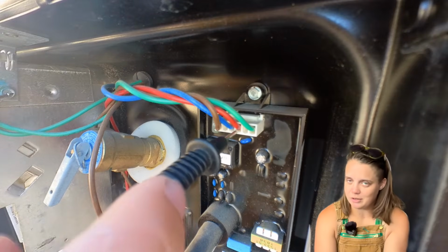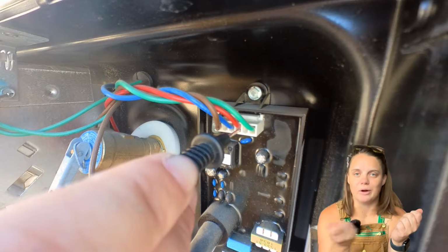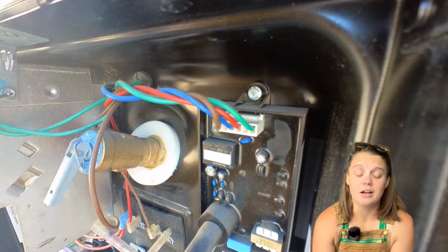So I have yet to have the igniter be the problem on a water heater, but hey, it does happen. So assuming that we've got 12 volts on brown, 12 volts on blue, and we are hearing a ticking noise coming from the igniter, then the next stop on our electricity journey is to look for 12 volts on red on the circuit board. Again, say it with me: one probe on the screw, one probe on the red wire.